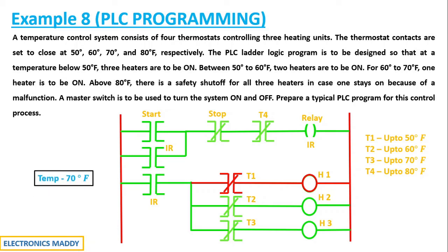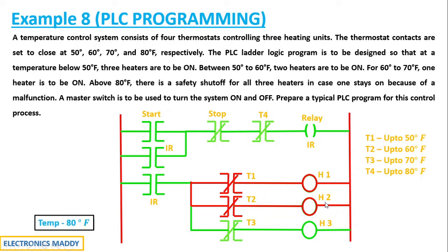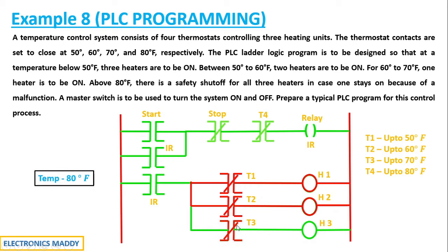If the temperature reaches 70°F, the heater corresponding to T2 should also turn off because it has an operating temperature of up to 60°F. Correspondingly, T2 acts as an open circuit, no current flows through that path, and H2 also turns off. Now, if the temperature reaches 80°F, T3 will be turned off — it acts as an open circuit, no current flows through that path, and heating unit H3 also turns off.